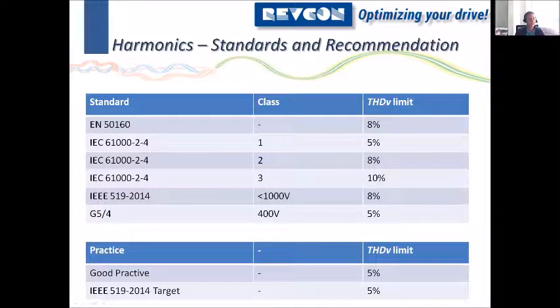So basically, all standards and recommendations will give you some limits, and some of them will give you some practical advice. So this is a quick overview. We don't have to go deep into this one, because I think in America, the most common one used is the IEEE 519. And also in Asia, in Germany, we use more or less all the other ones. The IEEE standard gives you a limit of 8%, which is a very high limit.